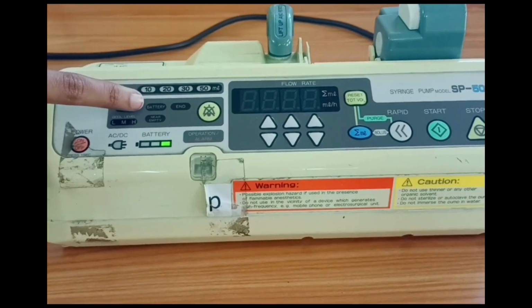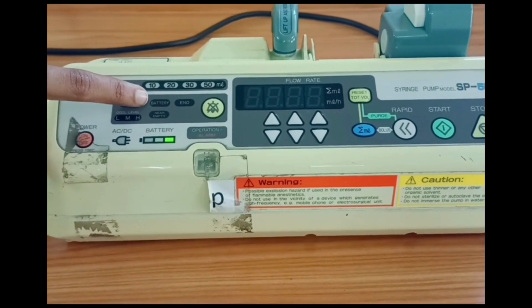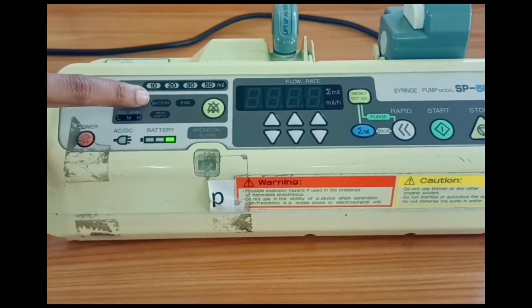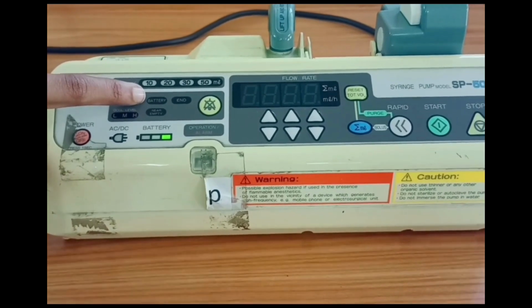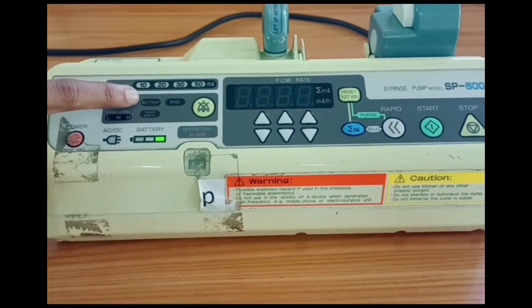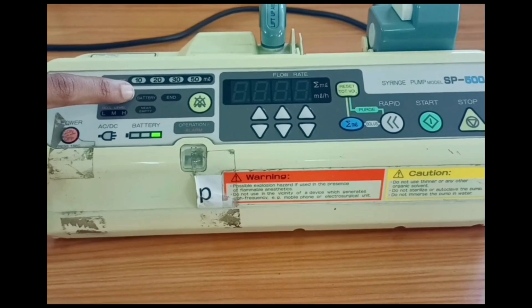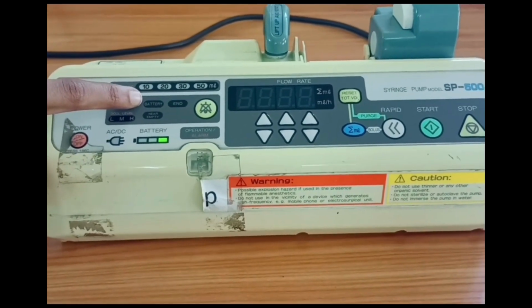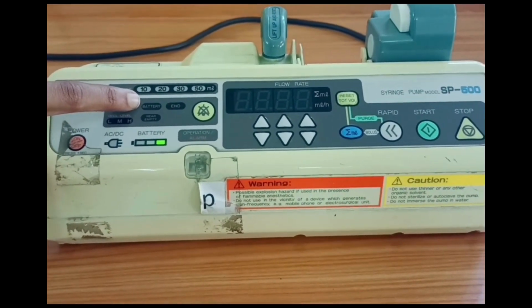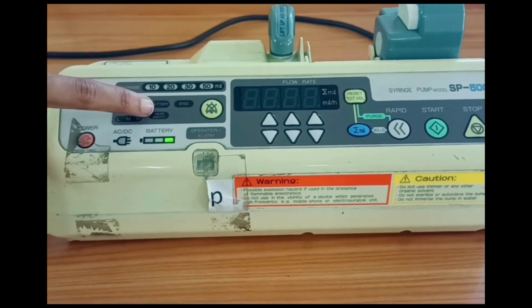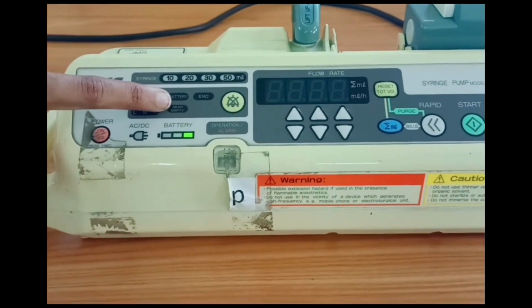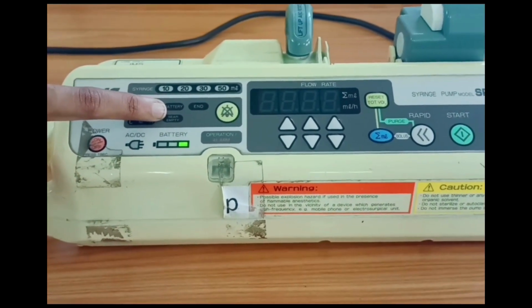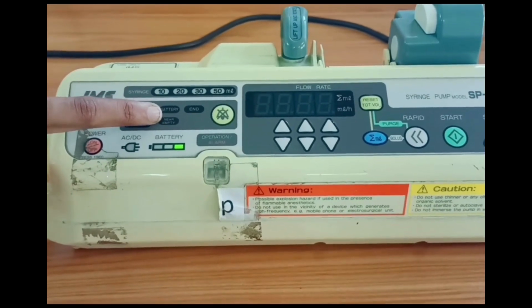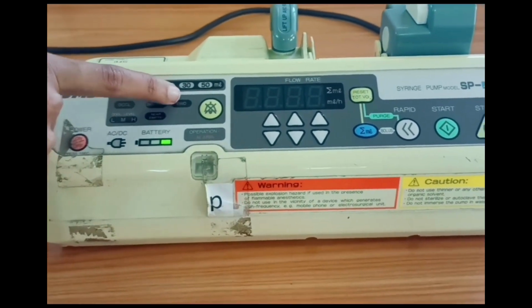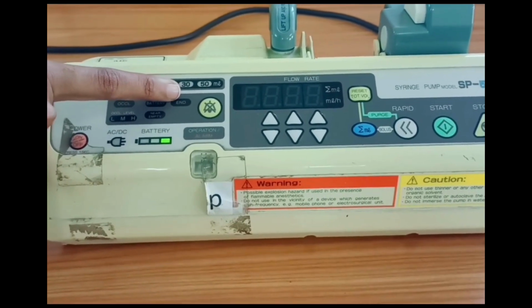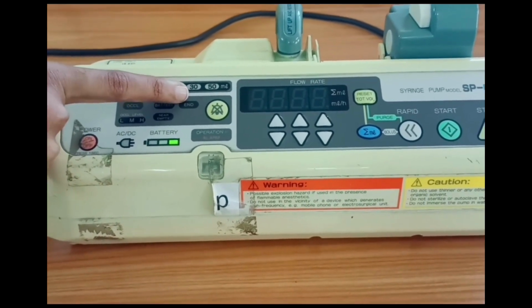This is the battery lamp. This lamp flashes if the voltage of the built-in battery becomes low. If the lamp flashes when the pump is connected to AC power, it is an alarm for battery deterioration. This is the near empty alarm. This lamp flashes when the fluid in the syringe becomes nearly empty. This is the end alarm. This lamp flashes when the infusion is completed.